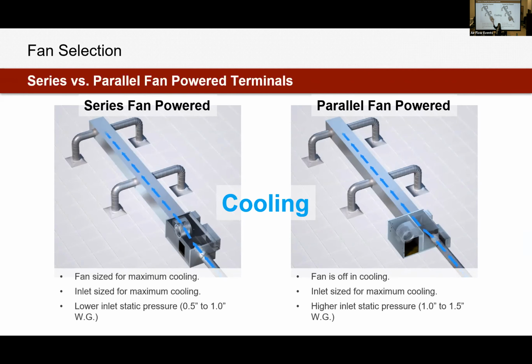We don't have to have high inlet static pressures on this valve because our fan is acting as a booster. So it allows us to take our air handler and turn the fan down a little bit because we don't need such high pressures on that inlet. Now in the parallel box, in cooling, we're acting just like a single duct. So again, we don't have this fan section here. The fan is off, it's not running. We are pushing air through this valve and it's going straight down the discharge, just like a single duct box. Because of that, we do have to have higher inlet static pressures on this inlet valve because it's just like a single duct. The fan gives us no assistance in cooling.